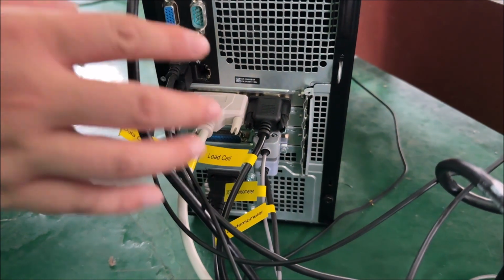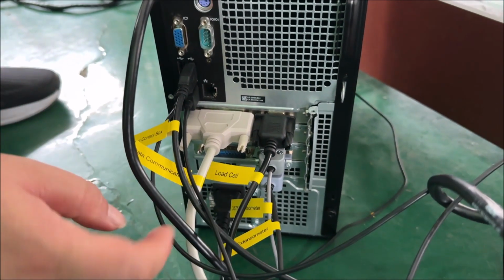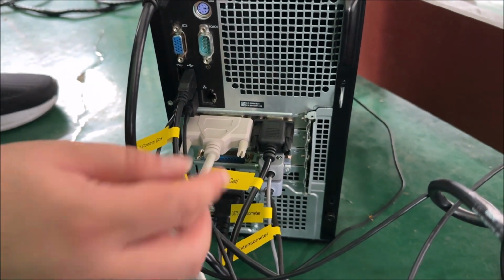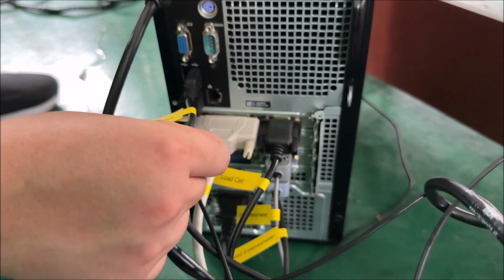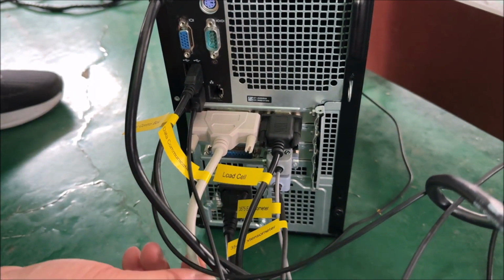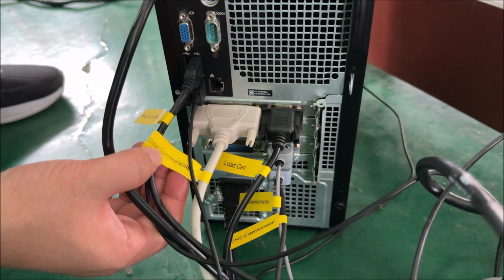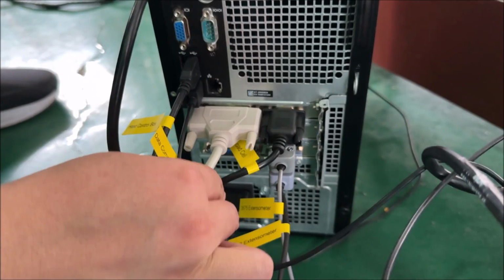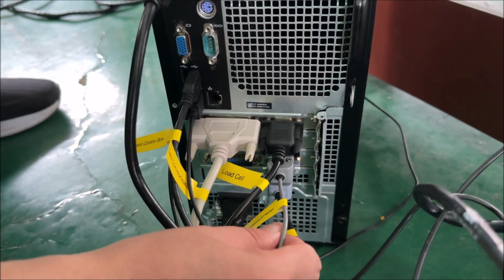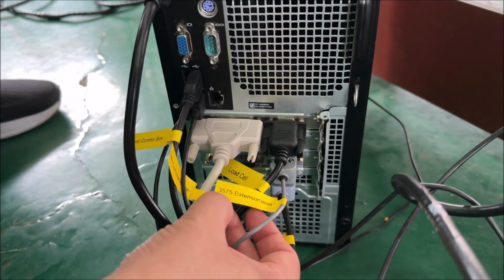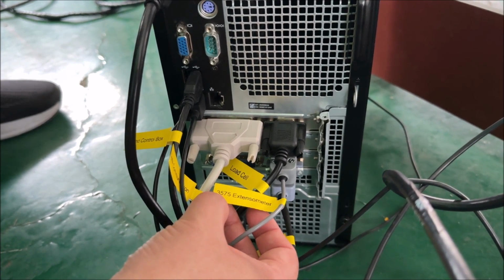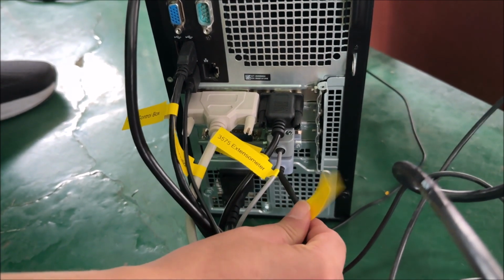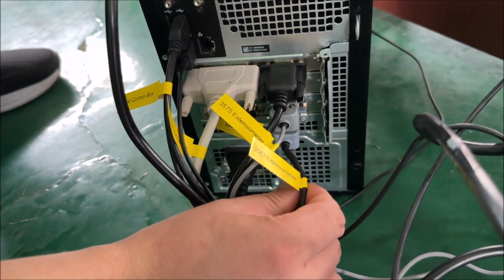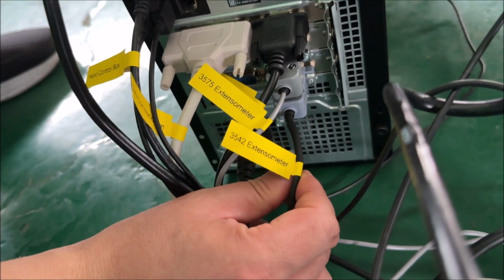This is the back of the computer. Connect these cables to the hand control box. The white cable is the data communication cable, which should be connected to the testing machine. Additionally, this is the load cell cable, while this is the extensometer cable labeled 3575 for one extensometer, and this one is labeled 3542 for the other clip-on extensometer.